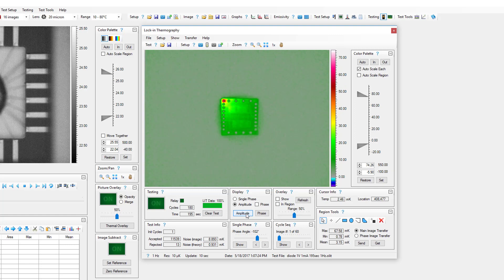Amplitude images display all temperature increases at any time during the cycle and are commonly used to determine fault location in the XY direction. Amplitude images are typically selected as the test image to update while a lock-in test is running.